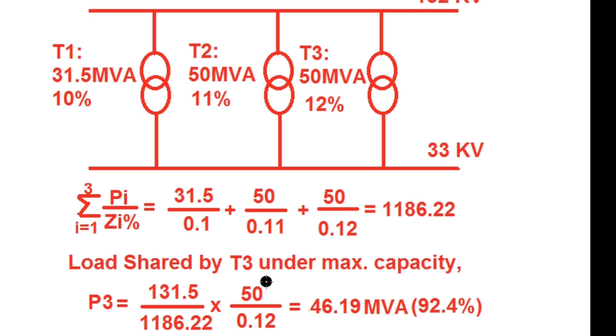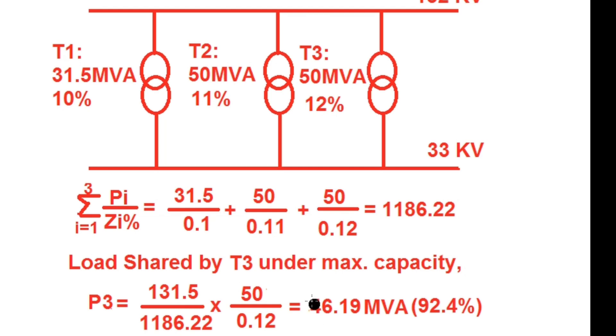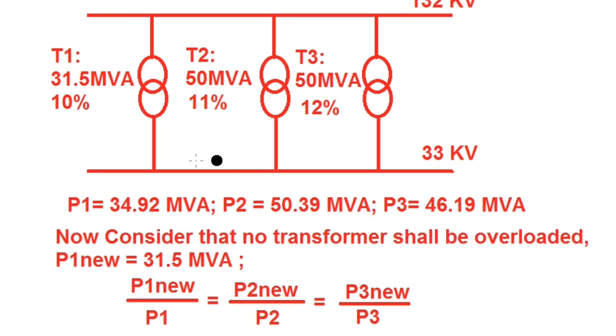The load shared by T3 is P3 = (131.5 / 1186.22) × (50 / 0.12), which comes to 46.19 MVA — running at 92.4% of full load capacity. In summary: T1 is overloaded at 111%, T2 is slightly overloaded, and T3 is underloaded under the maximum capacity condition of the substation.